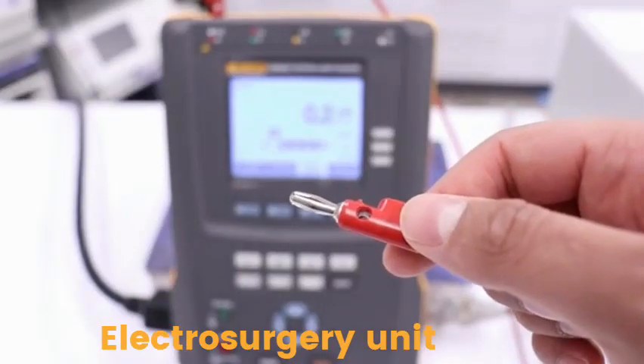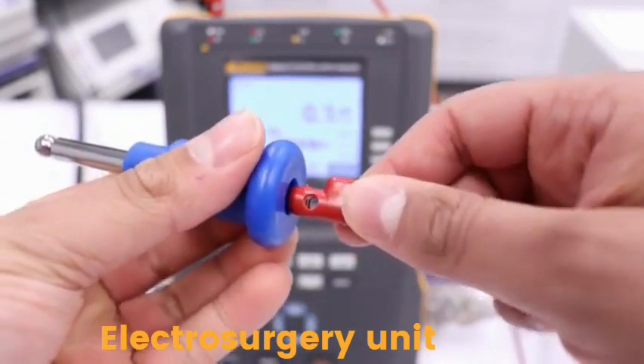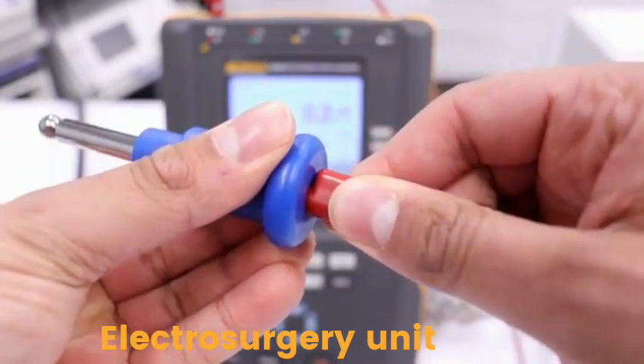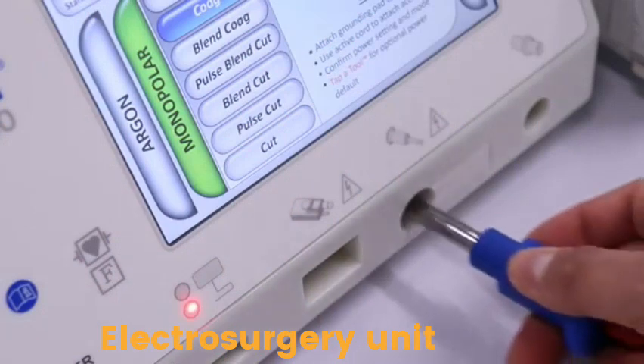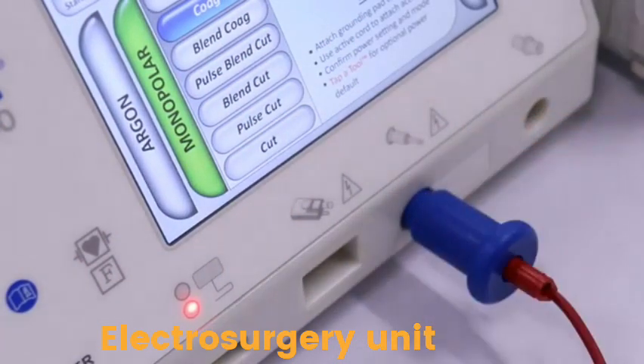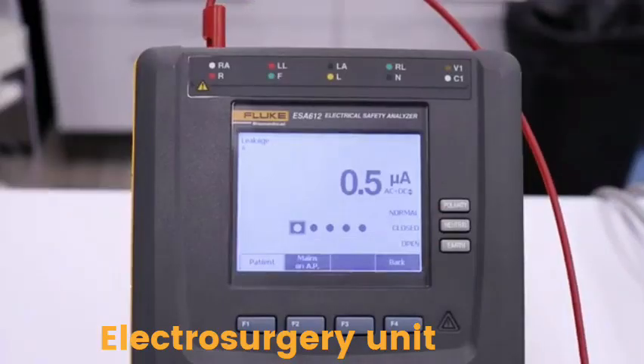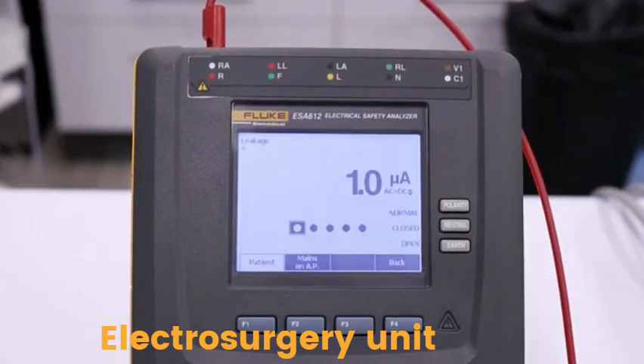Unplug the test lead from the argon receptacle and attach the monopolar test adapter. Plug the test adapter into the monopolar receptacle on the GI4000. Test for normal polarity, closed condition, and single fault open earth condition.